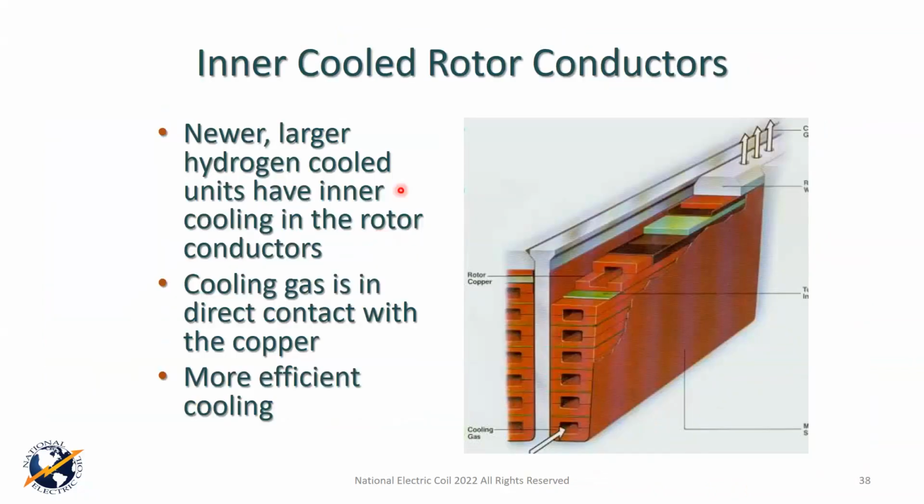All right, moving on. I showed you this picture earlier at the beginning. We were talking about inner cooled rotor conductors. You can see that joint I was telling you about earlier, where this machine is, instead of making this as a square tube with a square hole in the center of it, it's made in 2 C pieces that are folded into one another. And sometimes these are brazed together, sometimes not. In cases where they're not, there's been a phenomenon called copper dusting on some of those, and it can be corrected, and it's a maintenance configuration you got to worry about.